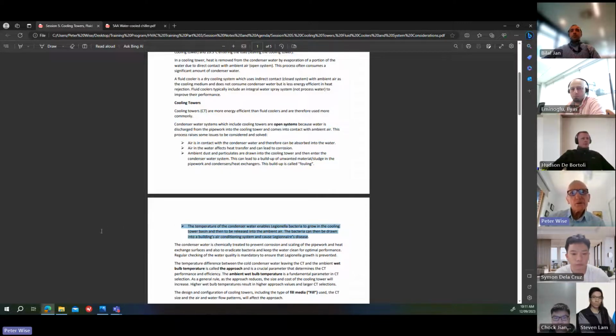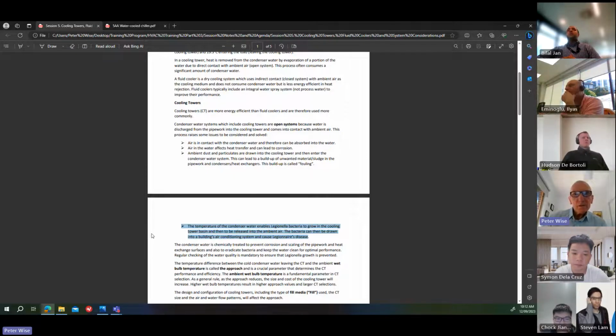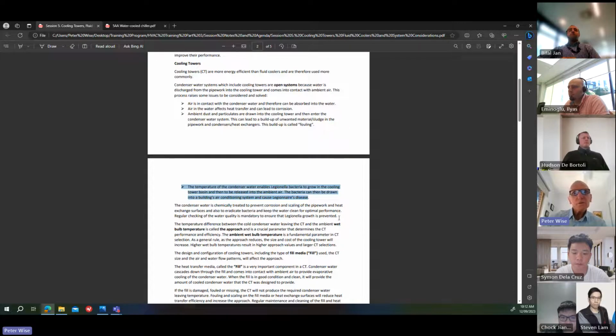Now, also very importantly, the temperature of the condenser water enables Legionella bacteria to grow. You've probably all heard of Legionnaires' disease, and it commonly comes from cooling towers. So the bacteria will grow in the cooling tower basin because of that ideal temperature for its growth, and then it can be released into the ambient air. So it forms pockets of bacteria in the cooling tower basin. And when the water is disturbed, some of those pockets can be released and blown into the air, and then can be drawn into a building's air conditioning system. And if that happens, Legionnaires' disease can occur. It gets into the air conditioning system, it's carried around, people breathe it in, and it's like a form of pneumonia. And it can be quite fatal. It has been fatal in many cases. So it's important to eradicate that or control it as best we can.